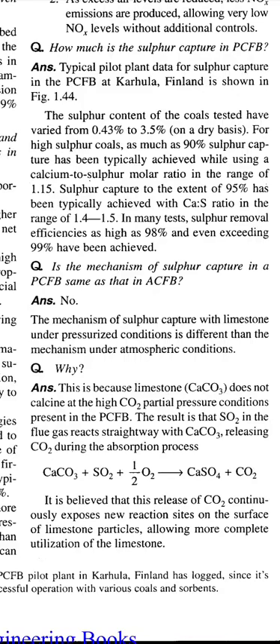For high sulfur coals, as much as 90% sulfur capture has been typically achieved while using a calcium to sulfur molar ratio in the range of 1.15. Sulfur capture to 95% has been typically achieved with a calcium to sulfur ratio in the range of 1.4 to 1.5. In many tests, sulfur removal efficiency as high as 98% and even exceeding 99% has been achieved.